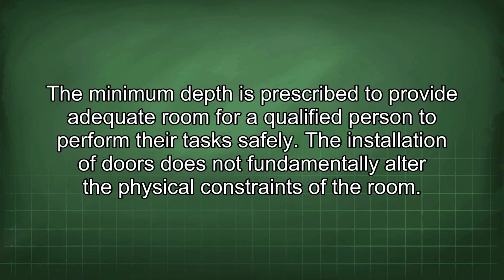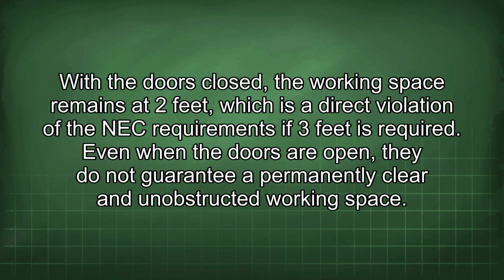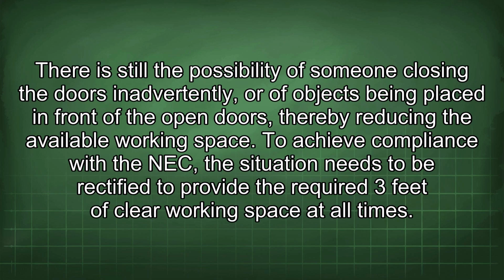The installation of doors does not fundamentally alter the physical constraints of the room. With the doors closed, the working space remains at 2 feet, which is a direct violation of the NEC requirements if 3 feet is required. Even when the doors are open, they do not guarantee a permanently clear and unobstructed working space. There is still the possibility of someone closing the doors inadvertently, or of objects being placed in front of the open doors, thereby reducing the available working space. To achieve compliance with the NEC, the situation needs to be rectified to provide the required 3 feet of clear working space at all times.